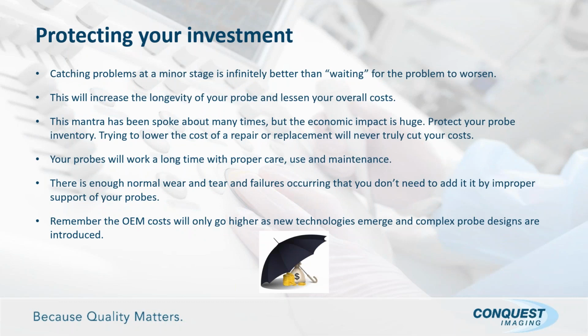Waiting until a problem gets worse makes me cringe. I've had people tell me, well, I know I've got a hole here in this lens, but I think I'll wait until it gets worse. Well, as soon as you do that, the problem's not going to get better. It is going to get worse, because you might get fluid or something else down in there and destroy your array. Now you went from a few $100 repair to thousands of dollars for a possible replacement of the whole probe. That just doesn't make sense to me. You're going to save money in the long run and protect that probe investment by handling it up front.